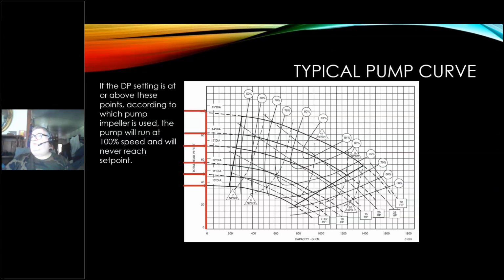Right. But then if you use your pump curve, you're going to see where my pressure differential is going to exceed my flow. And so that's where the zero flow line comes into play. These are the pressure differentials on the pumps, those curves that you cannot set your settings above. Do not set your settings above where those solid lines and the zones limit where you need to operate. Otherwise, you're just spinning. You're not going to pump water. You're just wasting energy. It'll run at 100%, but it'll never move any water. It's like deadheading the pump. Okay.